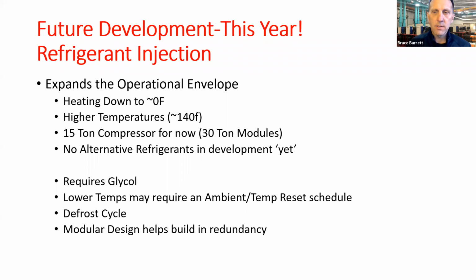The new technology is using refrigerant injected compressors, which expands the operational envelope all the way down to 0. We can heat up to about 140-degree hot water on the high end, again, depending on glycol percentage, etc. A 15-ton compressor is the only technology that's being shared right now with manufacturers such as us. So a 30-ton module is our limit. There are no alternative refrigerants in play yet, but there is chatter of the development of that.